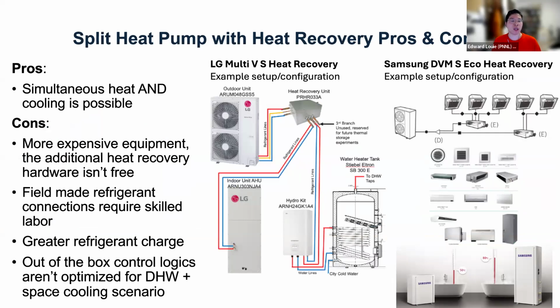So with split heat pumps, there's an additional category, which is split heat pumps with heat recovery. There are far fewer products in this category. Panasonic, LG, and Samsung are the three that I know of. And these systems allow simultaneous heating and cooling. That's made possible by a heat recovery unit. It's the 3-branch heat recovery unit that allows for quite a significant temperature difference between the heating side and the cooling side. And so you can be doing your domestic hot water reheat at the same time as air conditioning. And in theory, if you time it correctly, then the air conditioning waste heat can be recovered to go into domestic hot water.